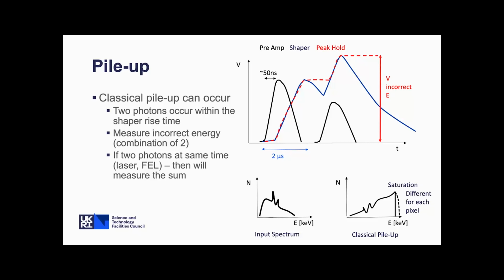In HEXITEC, because each pixel saturates at a slightly different voltage, if you see a peak at around 180 to 200 keV, the likelihood is that you're saturating your detector rather than it being a real peak. And that, again, is just a warning. To get classical pileup, with two events giving you the sum of the energies, that would only ever really occur in a pulsed source, so in laser-driven radiation or a FEL. So that's quite uncommon to happen. But you can also end up having effects similar to this, but at lower rates again.